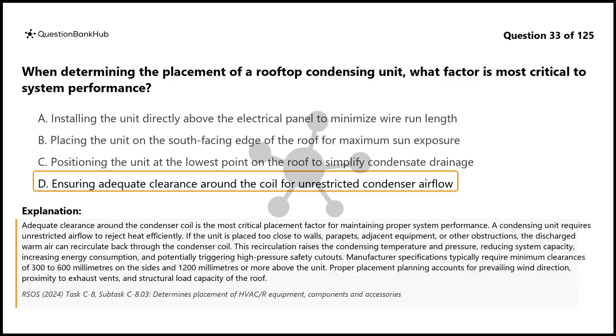Manufacturer specifications typically require minimum clearances of 300 to 600 mm on the sides and 1,200 mm or more above the unit. Proper placement planning accounts for prevailing wind direction, proximity to exhaust vents, and structural load capacity of the roof.